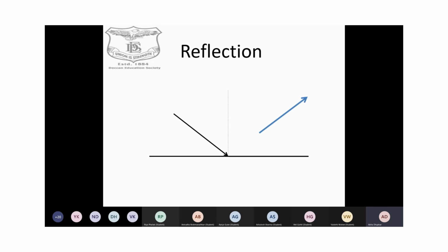The issue with low frequency currents is that they are targeted modalities. So over there the reflection is minimal as compared to high frequency modalities, or your proper radiations. We are concerned about attenuation in low frequency currents, but the fact is that their penetration itself in the tissues is very less.